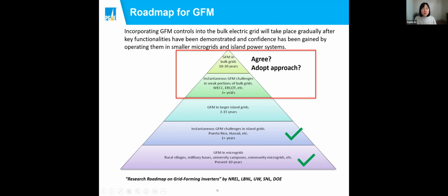So the top two point out maybe in potentially 3 or more years later, in different parts of the system for weak grid issues, that grid forming inverter could provide a better solution. And then for the 10 to 30 year time frame, grid forming inverter probably can be adopted in the bulk grid. I would think something like the WECC or the Eastern Interconnection or Texas.